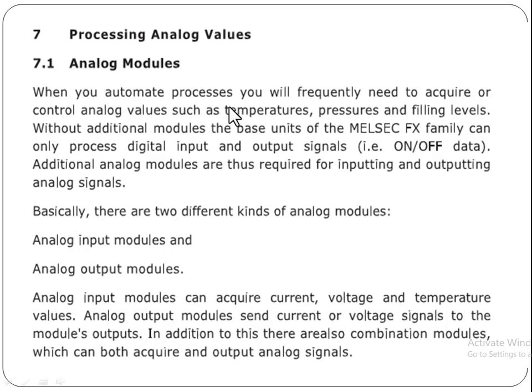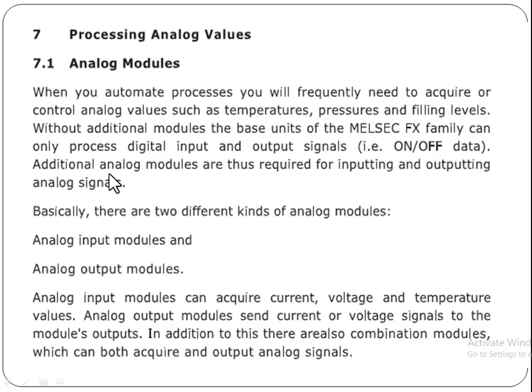When you automate a process, you will frequently need to acquire or control analog values such as temperatures, pressures, and filling levels. Without additional modules, the base unit of the Mitsubishi FX family can only process digital input and output signals — that is, on and off data. Additional analog modules are therefore required for inputting and outputting analog signals.